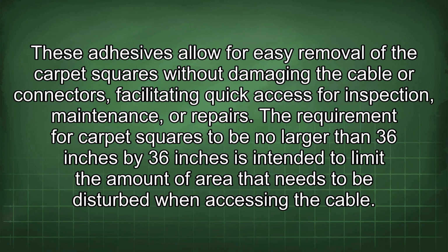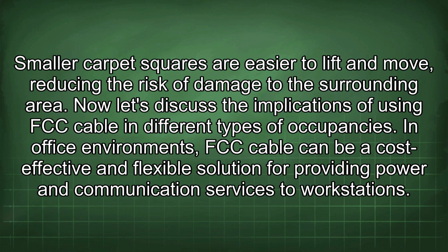These adhesives allow for easy removal of the carpet squares without damaging the cable or connectors, facilitating quick access for inspection, maintenance, or repairs. The requirement for carpet squares to be no larger than 36 inches by 36 inches is intended to limit the amount of area that needs to be disturbed when accessing the cable. Smaller carpet squares are easier to lift and move, reducing the risk of damage to the surrounding area.